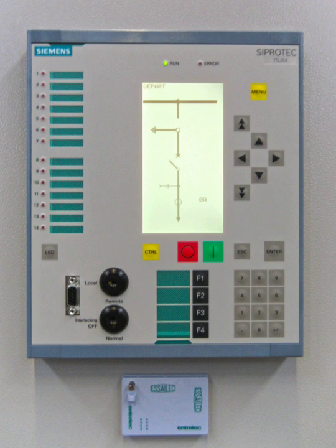Topic: Generator sets. In a power plant, the protective relays are intended to prevent damage to alternators or to the transformers in case of abnormal conditions of operation, due to internal failures, as well as insulating failures or regulation malfunctions. Such failures are unusual, so the protective relays have to operate very rarely. If a protective relay fails to detect a fault, the resulting damage to the alternator or to the transformer might require costly equipment repairs or replacement, as well as income loss from the inability to produce and sell energy.